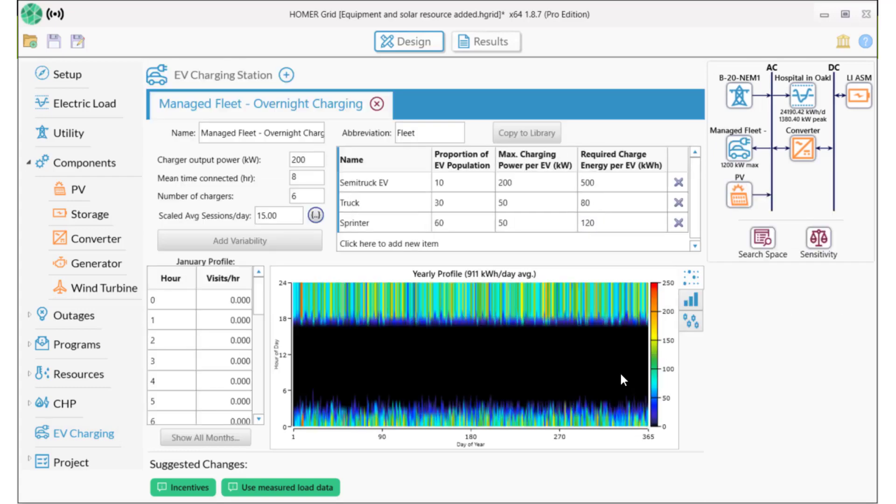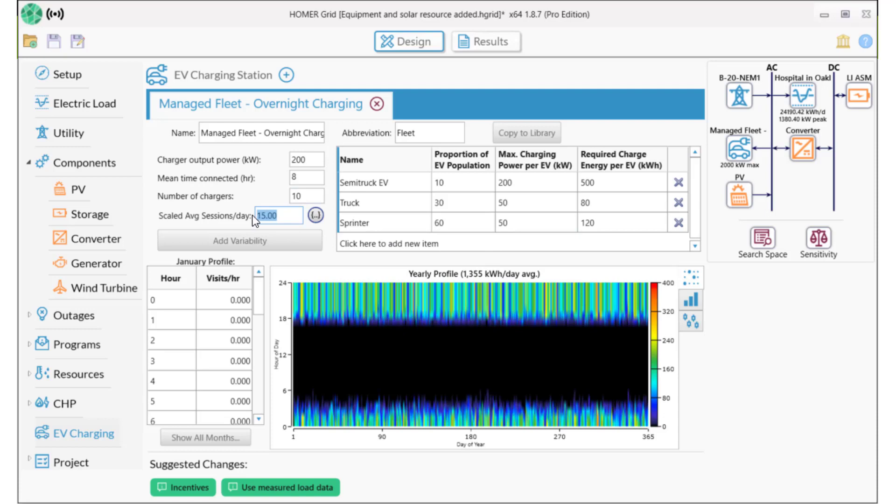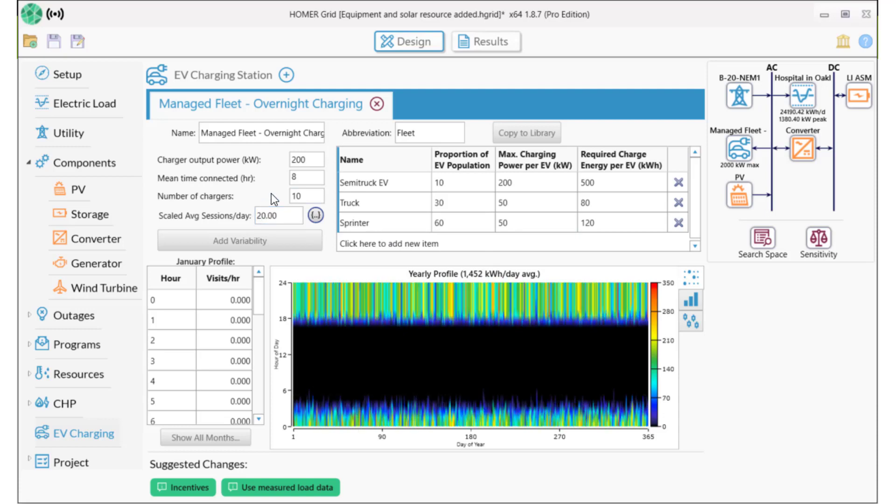This profile is for large vehicles. It uses a 200 kW outlet with a mean charging time of eight hours, six chargers, and an average of 15 sessions a day. We're going to change this to 10 chargers and 20 sessions a day. So we're going to add up to 2,000 kW of load onto our system.